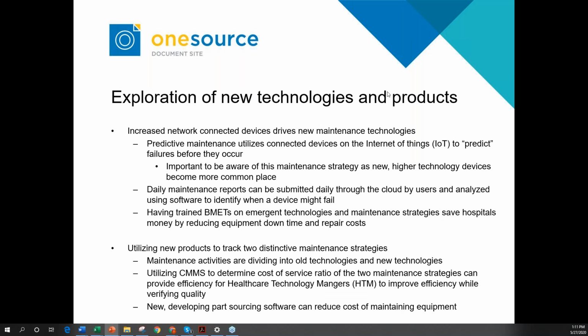And another way to streamline your preventative maintenance process is the exploration of new technologies and products. With the increased amount of network connected devices, it's going to drive new maintenance technologies. One thing that looks like it's emerging is predictive maintenance, and it utilizes connected devices on the Internet of Things to predict failures before they occur. This is different than standard preventative maintenance, where you go to prevent the problem based on a manual or a set of rules that this is going to fail at this time. This is actually predictive, so it gives you live feedback on how the machine is performing and the different data points that you need to look at to identify a small failure and fix it before it causes a larger one. So it's pretty exciting to see this new technology come into the medical world.